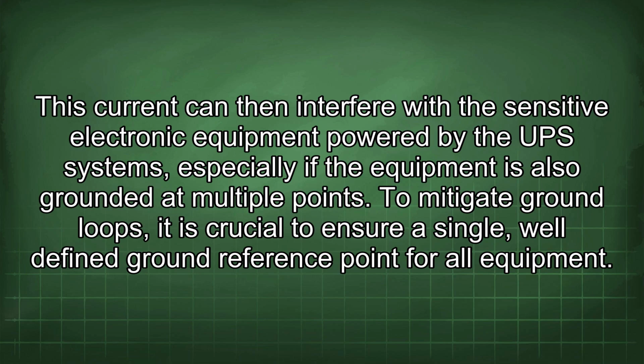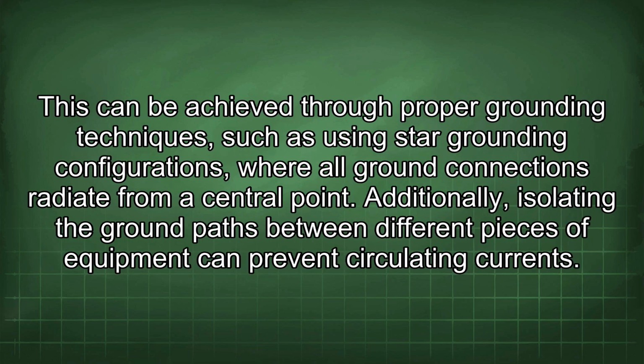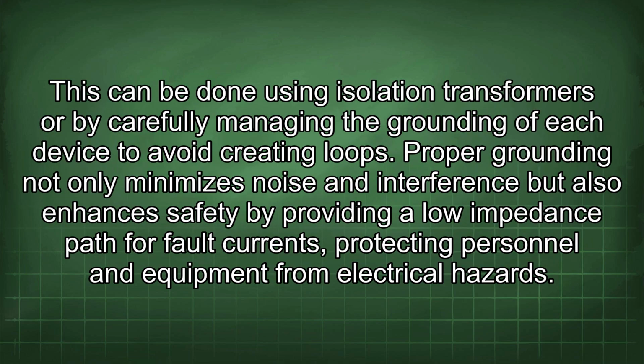To mitigate ground loops, it is crucial to ensure a single, well-defined ground reference point for all equipment. This can be achieved through proper grounding techniques, such as using star grounding configurations, where all ground connections radiate from a central point. Additionally, isolating the ground paths between different pieces of equipment can prevent circulating currents. This can be done using isolation transformers or by carefully managing the grounding of each device to avoid creating loops. Proper grounding not only minimizes noise and interference but also enhances safety by providing a low impedance path for fault currents, protecting personnel and equipment from electrical hazards.